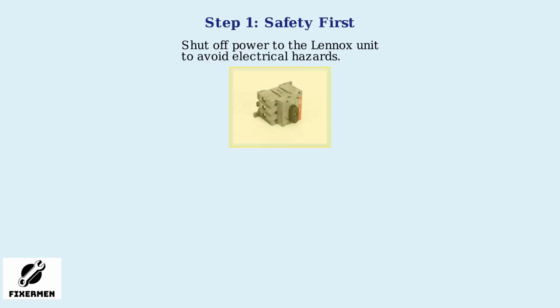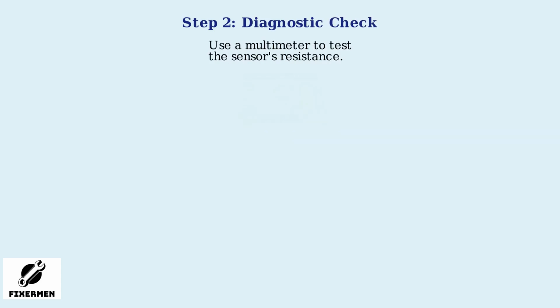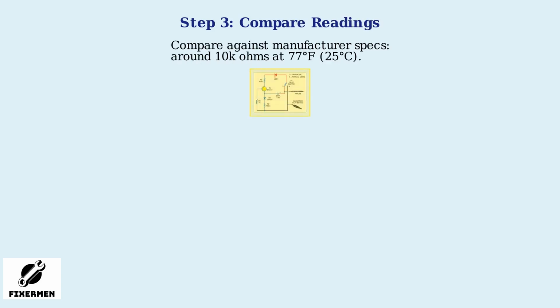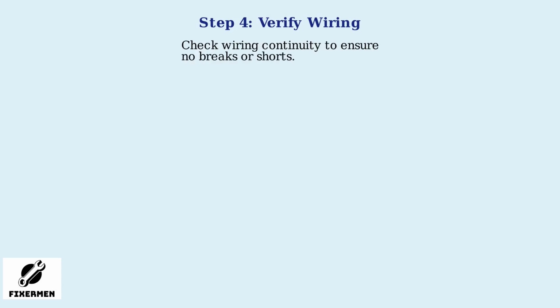Before attempting any repairs, safety is paramount. Always shut off power to your Lennox unit to avoid electrical hazards. Next, perform a diagnostic check using a multimeter to test the sensor's resistance. Compare your readings against the manufacturer's specifications, typically around 10 kiloohms at 77 degrees Fahrenheit or 25 degrees Celsius. Also, verify the continuity of the wiring to ensure there are no breaks or shorts.